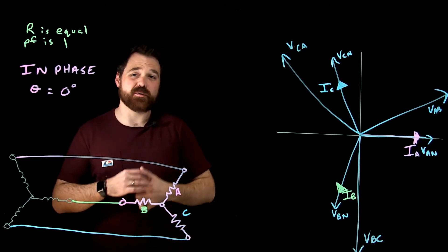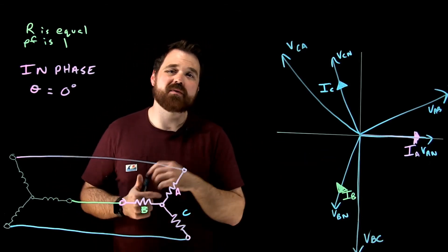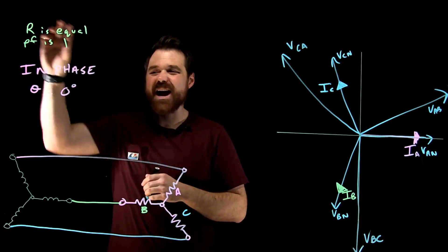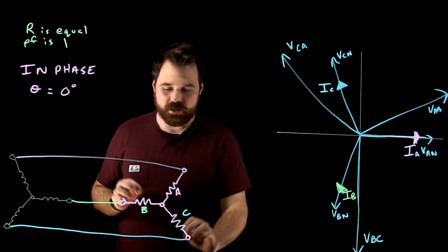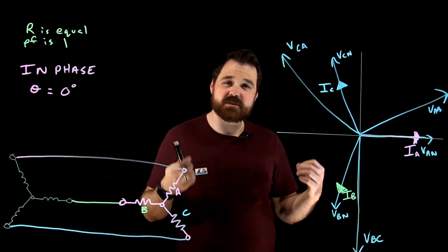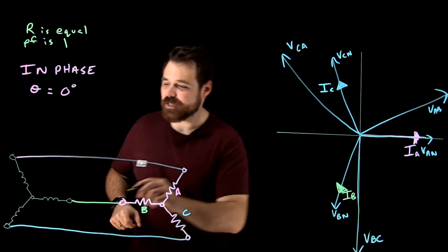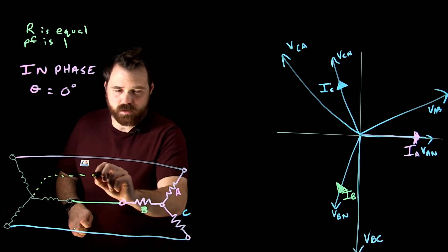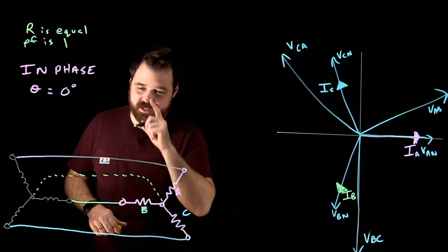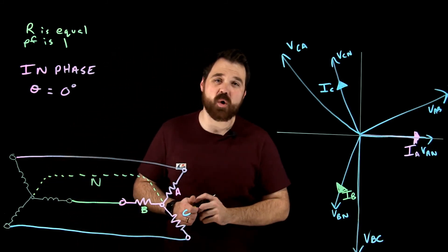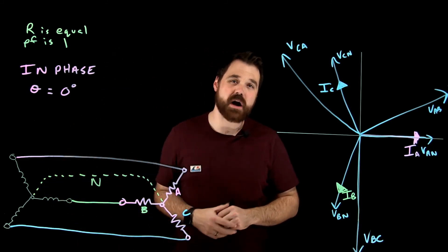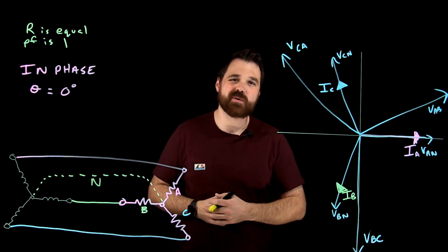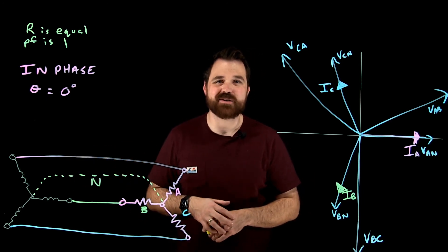So that's kind of what your phasor diagram would look like for a purely resistive balanced three-phase load. Now the big thing with that three phase balanced load is that because everything is balanced, there is no current going to be flowing on that neutral conductor. So in a balanced load, we're not going to see any current flowing back on that neutral.